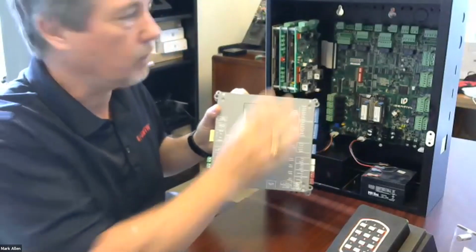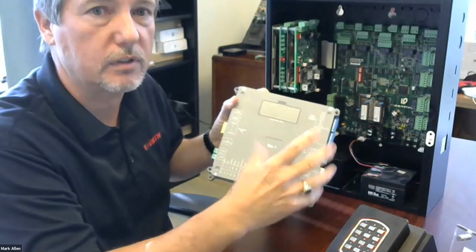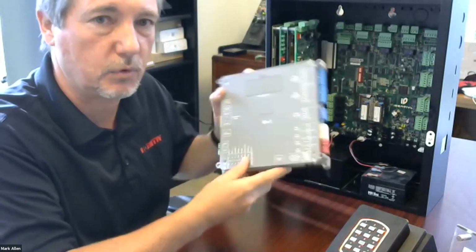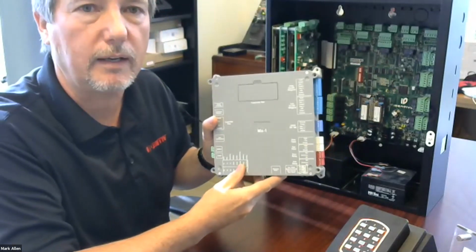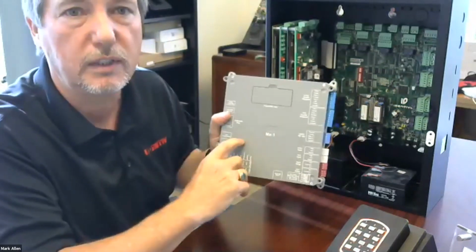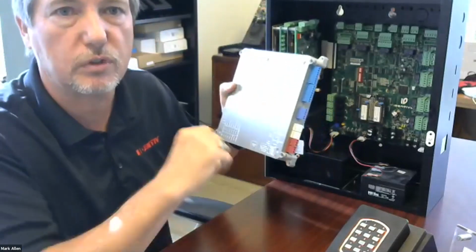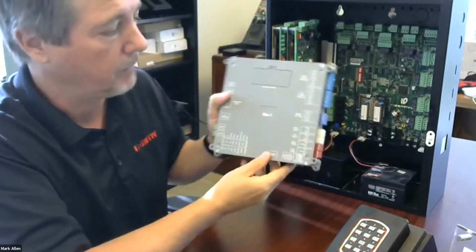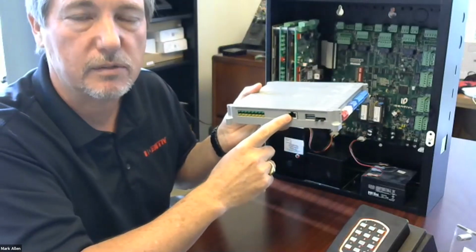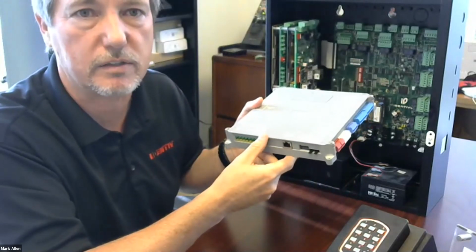It's basically all of the components that are on this 8-door controller have been removed, so you only have enough components for 1 door. It's put into a device that's a bit more easy to manage, a bit more easy to move around, and it reduces the long wire runs. So this product usually gets installed above the door, usually on the secure side of the door. The readers are wired into the connectors here, so you have a short run from above the door down to a reader, and then it gets connected via a PoE connector. So it gets its power from an alternative source, usually a PoE switch that's in an IT closet somewhere.